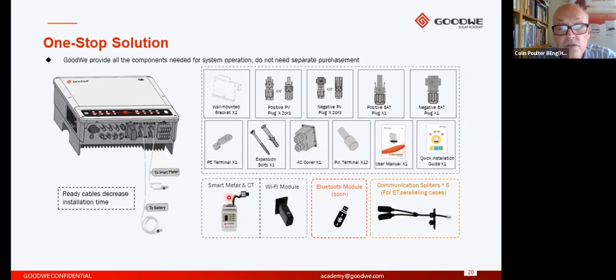The smart meter is usually located at the incoming point to the building, because the CT clamp to which this smart meter is connected needs to be monitoring the incoming point. That CT clamp cable length is around 1.5 meters, and this cable length cannot be extended, which is why this device needs to sit at the incoming point of the building. The distance between where this is located and where you locate the inverter will depend upon whether you need to extend the smart meter cable. You can extend it up to 100 meters, but it's only this cable that you can extend.